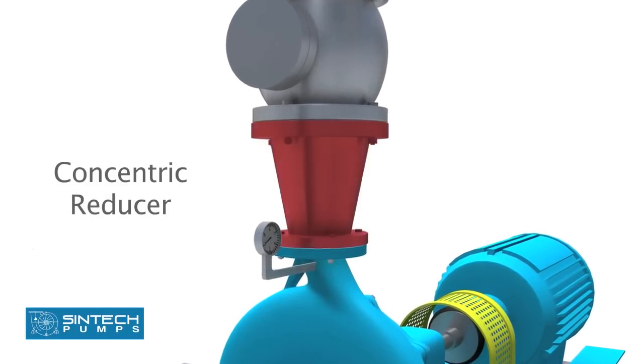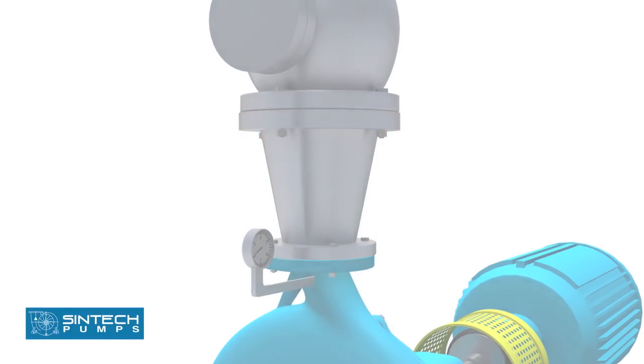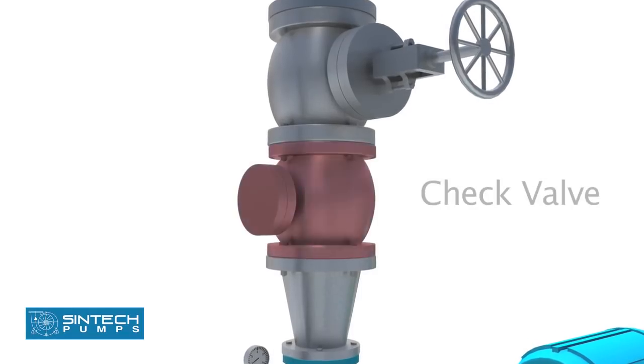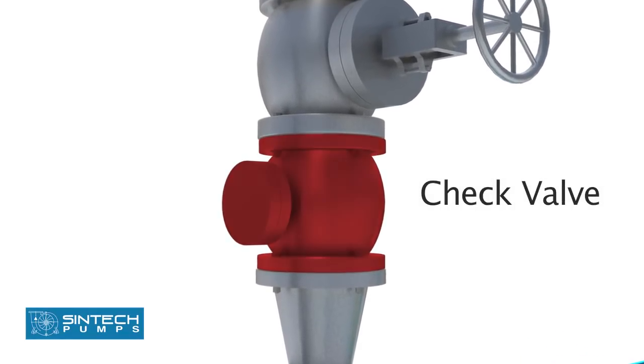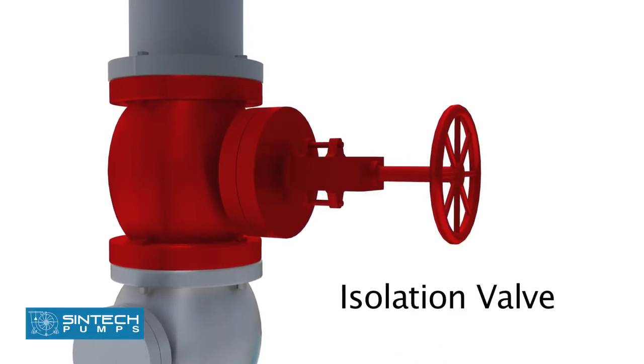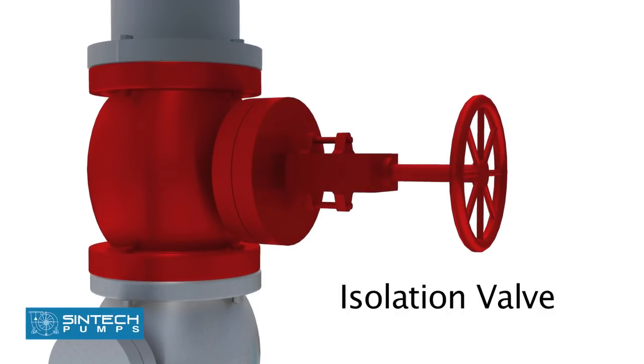Concentric reducers are installed in the discharge pipe to minimize friction losses. The check valve used in the discharge should be of non-SLAM type to prevent hydraulic shocks. The isolation valve is provided downstream of the check valve so that these can be taken up for servicing whenever required.